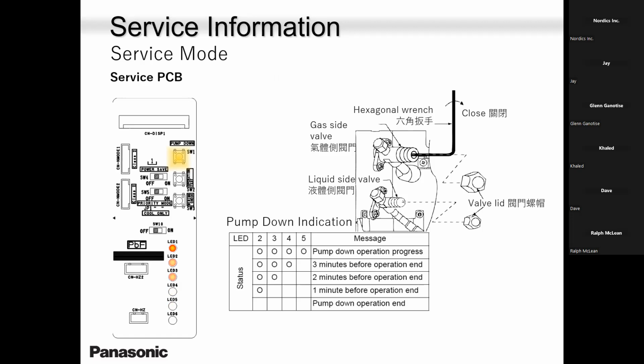As you can see, the procedure is the same like any other system to pump it down. Close the liquid line first, the small pipe, and then keep your Allen key ready on the suction line, so that when you're about to get close to zero, you are pretty fast to close the gas line, vapor line, suction line.